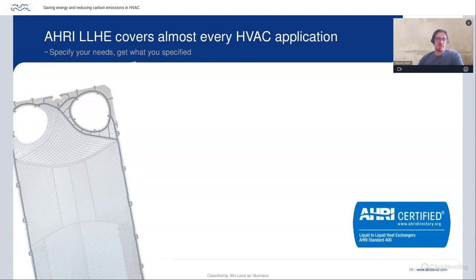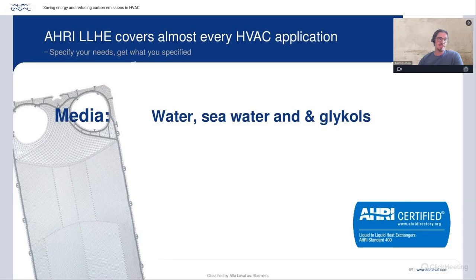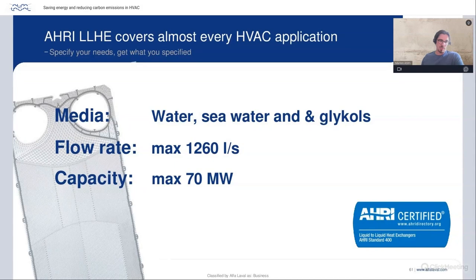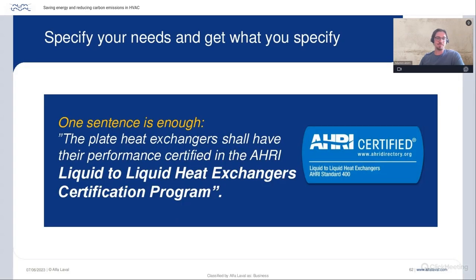Scope-wise, AHRI is covering basically everything within HVAC. Media-wise, it's water, seawater, and glycols, which are the most common ones used in HVAC applications. The flow rate is very big, 1260 liters per second, which turns into huge capacity. One unit can have up to 70 megawatts, and it's very seldom that we see HVAC applications having more capacity than 70 megawatts. Very, very seldom. So basically, if it's an HVAC application, you can demand AHRI performance certification.